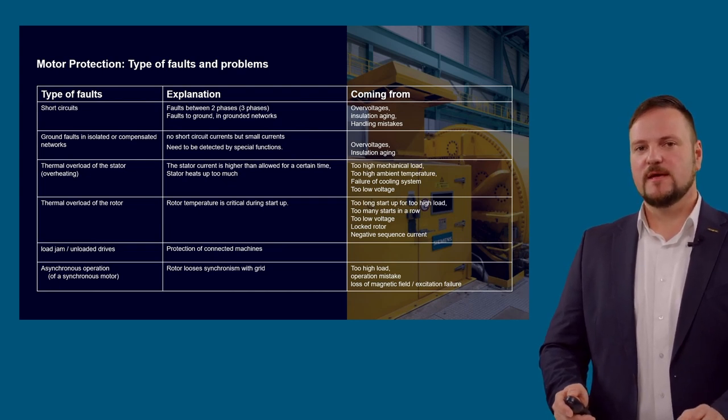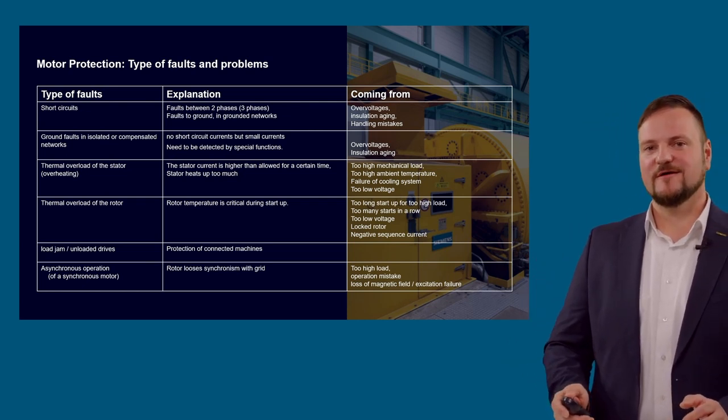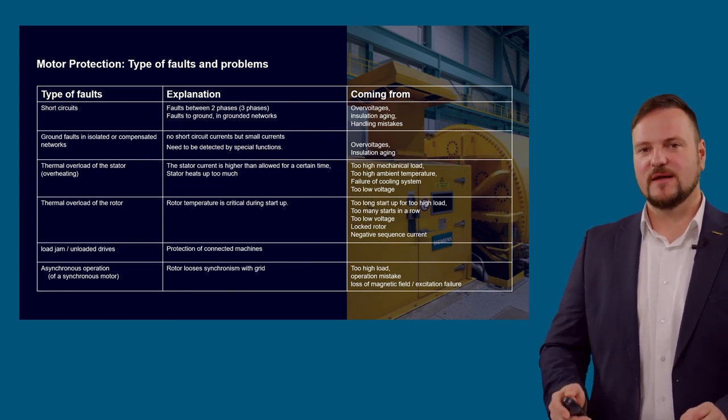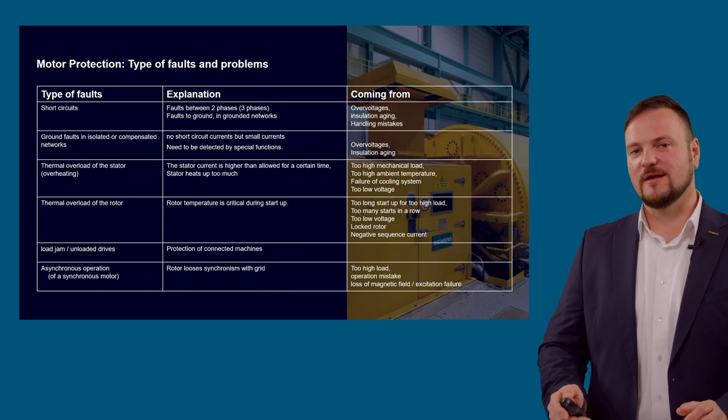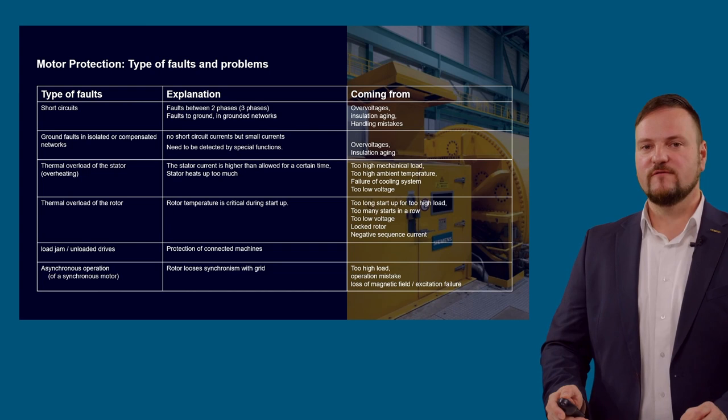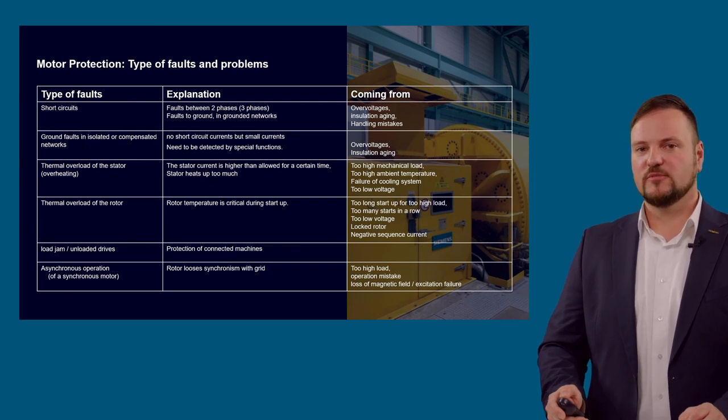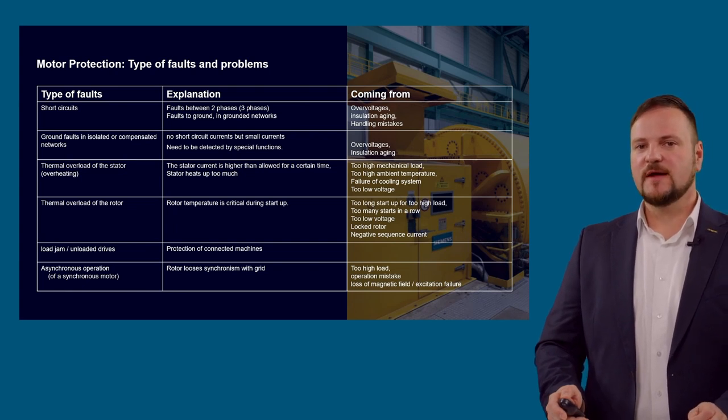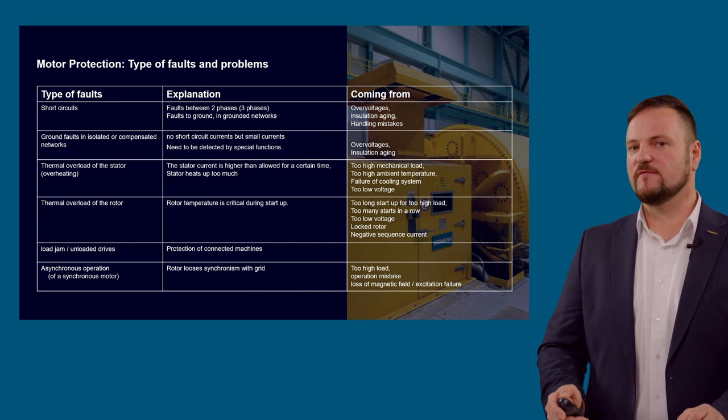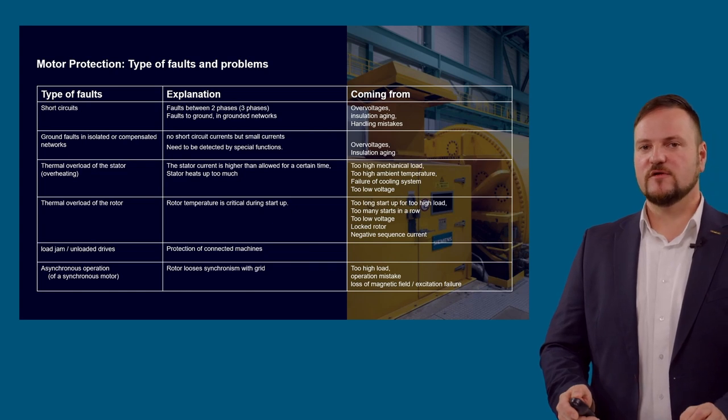A motor stator can be overheated when the load current is higher than the permitted current for a longer time, and the rotor is especially thermally stressed during startup, or even worse, when the rotor is blocked completely. Then we have some functions that also protect the driven load: detection of unloaded drives like pumps which could get damaged without load, protection against load jam to protect bearings and gearing. Finally, for synchronous motors, 7UM and 7SX85 provide under-excitation functionality against loss of field and asynchronous operation.